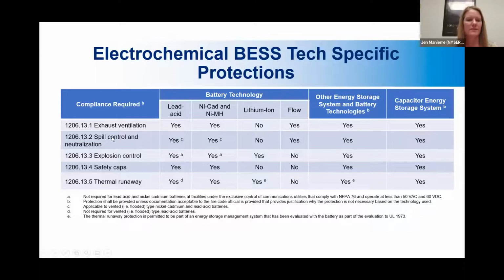However, if you skip down 2 rows to explosion control, and move over to the lithium ion column, you will see that explosion control is absolutely required for lithium ion because they can off gas when something goes wrong. And one way that you can meet the explosion control requirement in the fire code is by using exhaust ventilation. So you might see it with them, you might not, you probably will though. I think most of these systems are going to have some sort of exhaust no matter what.